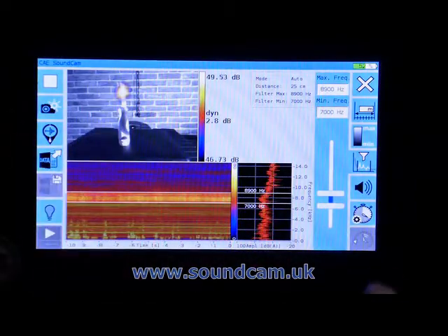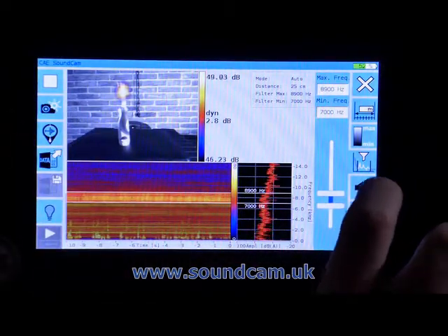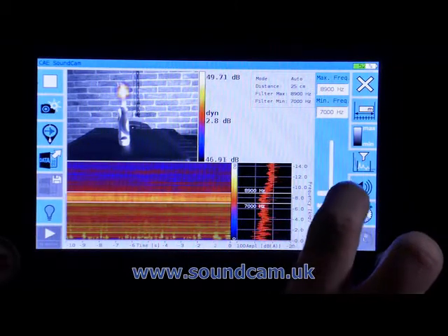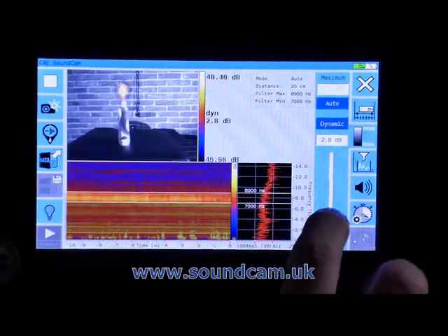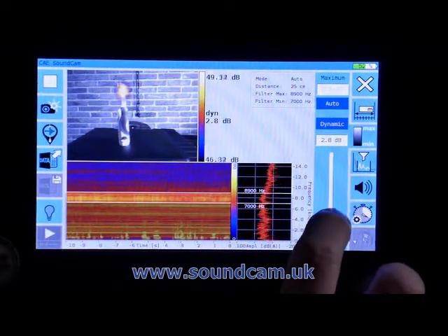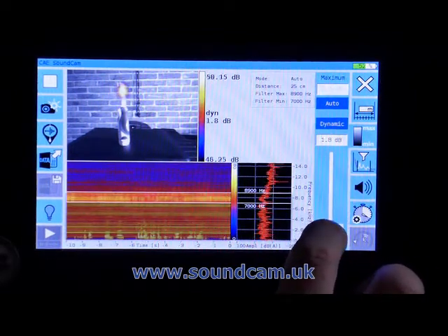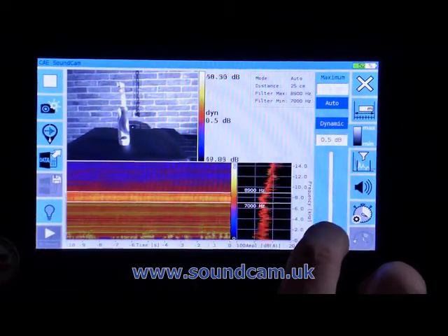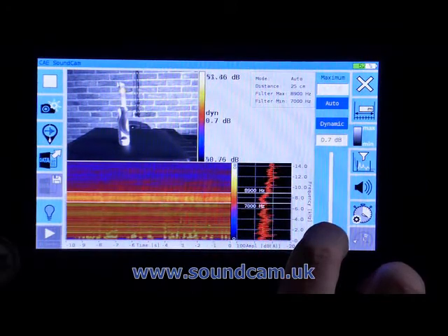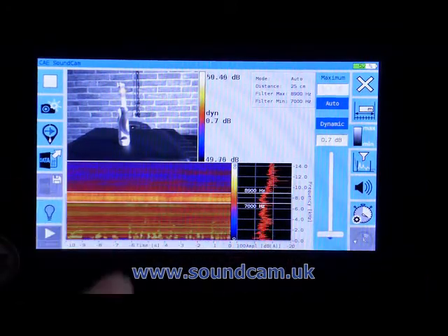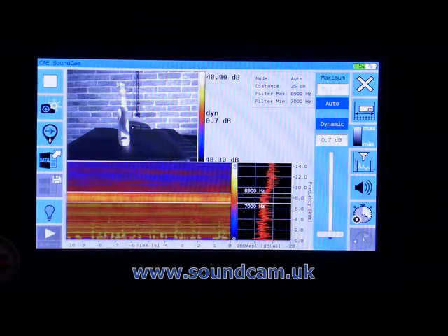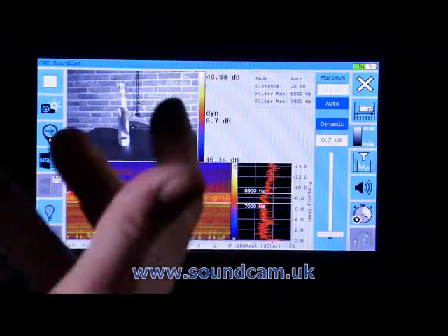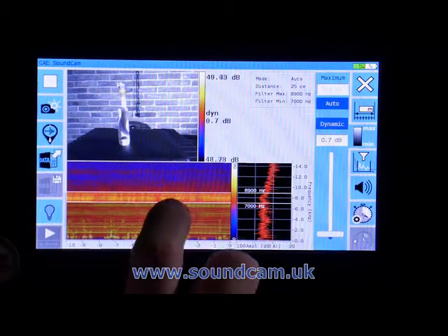I can leave it on this one if you like, then you see both pictures at the same time. And if I go down on the dynamic range again, because it's a lower frequency, they always have more energy, you can see again we're looking in a similar area to before actually. Very similar. It might be slightly lower down than the actual rotating part, but very similar frequency area. So even that area, which is an annoying area, is also coming from that same location on your machine. Could be any kind of machine, of course.